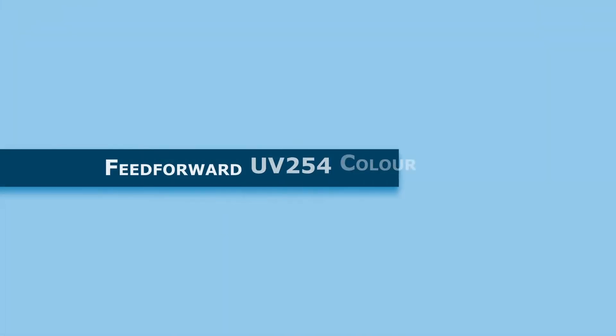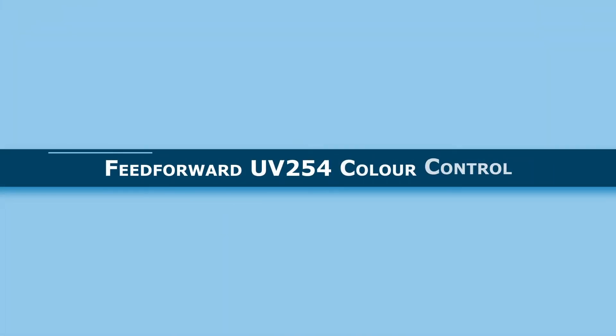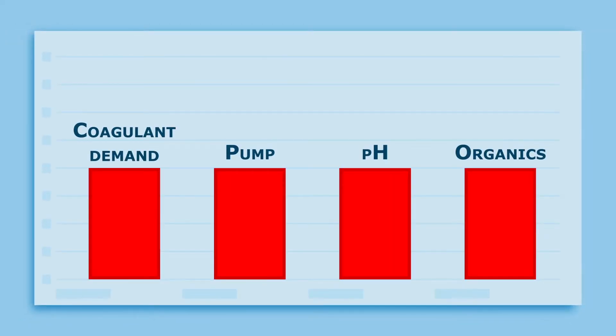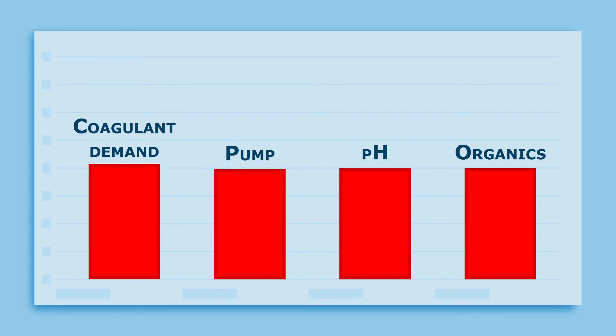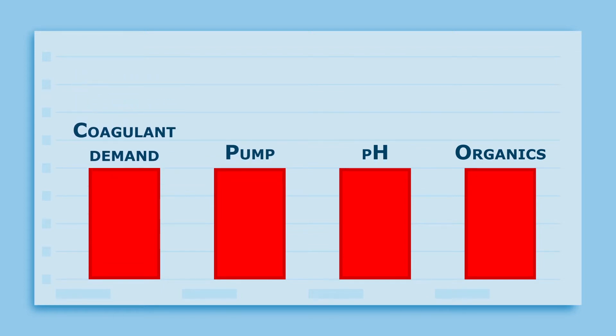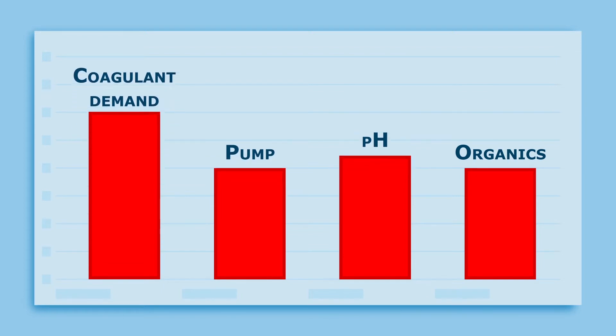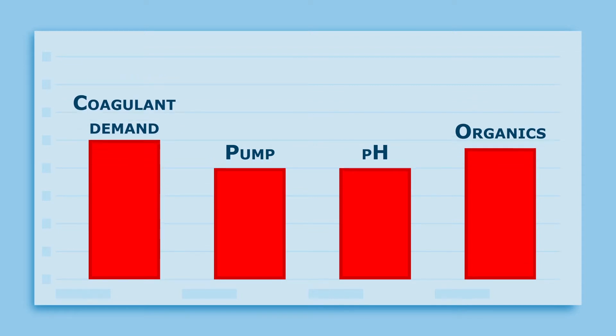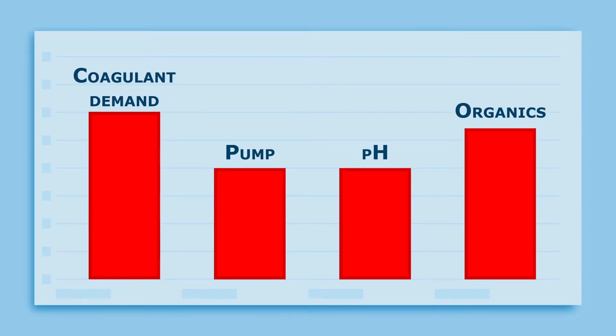Feed forward UV-254 or colour control also frequently leads to incorrect dosing because of coagulant, pump and pH variability, as well as changes over time in the UV-254 or colour to TOC correlation due to changing organics.